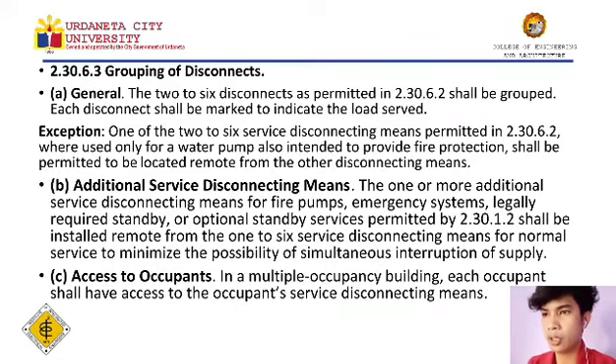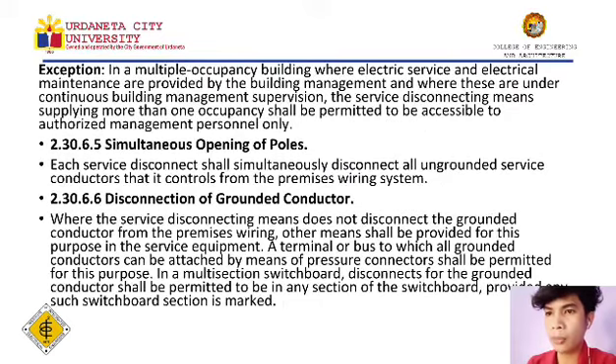And the third is access to occupants. In a multiple occupancy building, each occupant shall have access to the occupant's service disconnecting means. Exception: in a multiple occupancy building where electrical service and electrical maintenance are provided by the building management and where these are under continuous building management supervision, the service disconnecting means supplying more than one occupancy shall be permitted to be accessible to authorized management personnel only.